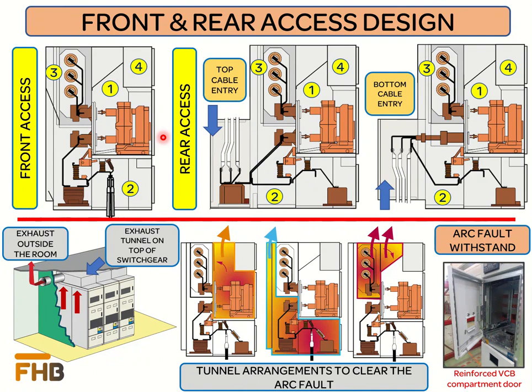If the power cable is connected at the rear side of the switchgear, then it is called the rear-access design. In the rear-access design, power cables can either enter the switchgear from top or through bottom. It is important to mention that rear-access switchgear require operator access from rear side for maintenance. Therefore, free space according to manufacturer's recommendation should be left for this purpose behind the switchgear.